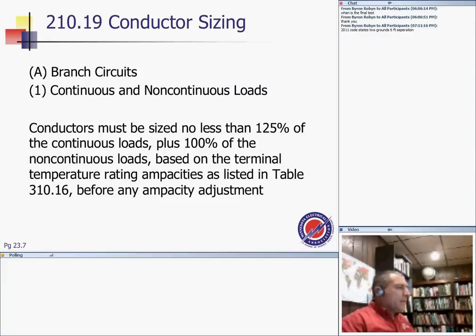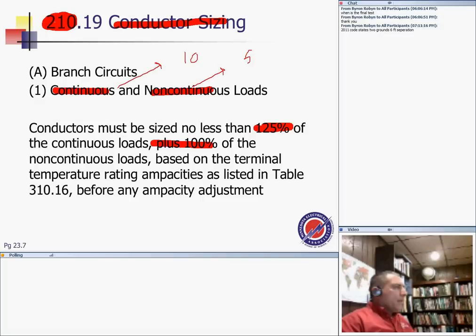So a little bit about the branch circuit now. We're talking about 210.19, as you all know, conductors. How do you size a branch circuit conductor? You take the branch circuit continuous load and non-continuous load. You take 125% of the continuous load plus 100% of the non-continuous load. Example: let's do a very simple example, guys. I have a machine that I want to size, and that machine has 10 amps continuous, and also inside this machine there's 5 amps non-continuous. So how do you size a conductor for it? No problem. You multiply the continuous one by 1.25, and then you add the non-continuous to it. So give me 12.5 plus 5, and that means 17.5 amps, continuous and non-continuous.